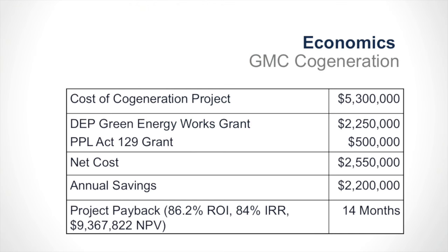So what we've done - and this is what the project looked like - we started out with a project that was $5.3 million. We were very fortunate to get an ARRA grant from the federal government for $2.25 million, and a grant of $500,000 from PP&L. The project cost about that. Our first year of operation, we saw our cost decrease $2.2 million, for a payback of 14 months. This has since increased, because we were venting some exhaust, so we installed a steam turbine chiller to use that heat, and by doing that we got an additional 1,500 tons of air conditioning for free, because it was waste heat at that point. We're able to make air conditioning out of that with the steam turbine chiller. So now we're up to about $2.5 million a year in savings.